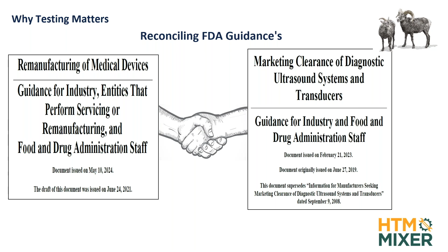Let's look at an ultrasound probe real quick. Reconciling the FDA documents. Like I said, all you have to do is type in the words FDA ultrasound clearance, and this will pop up on your Google screen, and you say remanufacturing or servicing, and this document will pop up. So the key here, and why testing matters, is so that we can reconcile what those two documents are asking for from the FDA, so that we could show you and also the FDA that our activities are restoring the device to its original specifications, okay? Substantially. They always allow variances because even OEMs have variances.